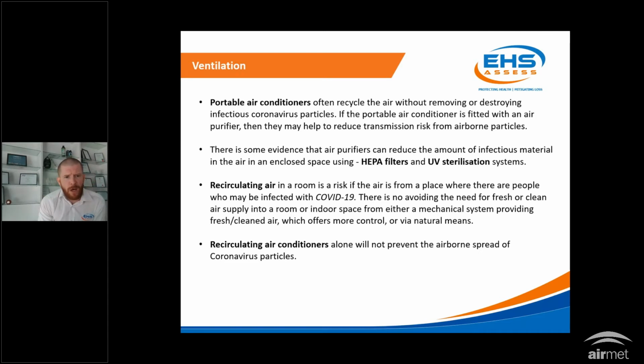Recirculating air is a big one. Recirculating air occurs when we don't have a method of introducing fresh air into the building. A great example is the wall-mounted split system we saw a couple of moments ago. They don't bring any fresh air into the building - they basically work on the principle of passing recirculated air over a coil, which heats up or cools down. So wall-mounted split systems, while good from a thermal comfort perspective for heating and cooling, aren't offering huge value in controlling the virus.